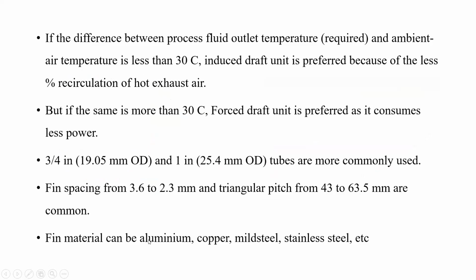And fin material can be aluminum, copper, mild steel, or stainless steel, depending upon the heat removal required, because thermal conductivity depends upon the material, and as thermal conductivity increases, rate of heat transfer increases. So if your heat removal requirement is high, you will have to choose a material with higher thermal conductivity.